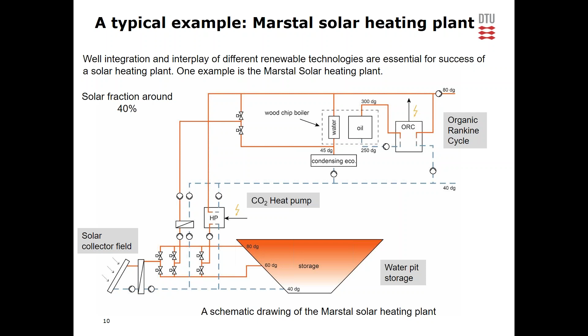This is one example, the Marstal Solar heating plant, which Jan-Erik has already mentioned, but I will focus on the system point of view. There's a water pit storage and solar collector field, and the boiler is a wood chip boiler combined with ORC, which can generate electricity. The system also uses a CO2 heat pump. The solar fraction is around 40%, or even up to 50% depending on the year. Because of the heat storage, good integration and interplay of different renewable sources could be realized.